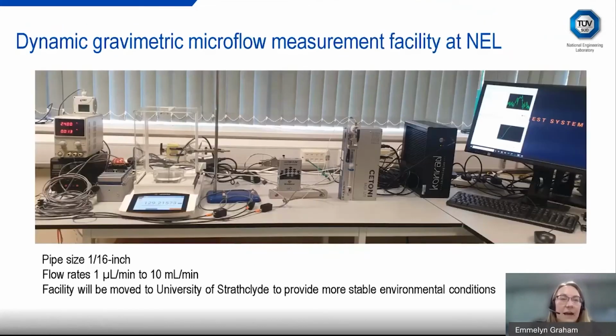This is an example of a gravimetric calibration setup that we have at NEL. We have our syringe pump, we have an inline flow meter, we have different pressure sensors, temperature sensors, we've got our precision balance, and we have our data logging instrumentation. This is actually for much higher flow rates, from 1 microliter to about 10 milliliters per minute.